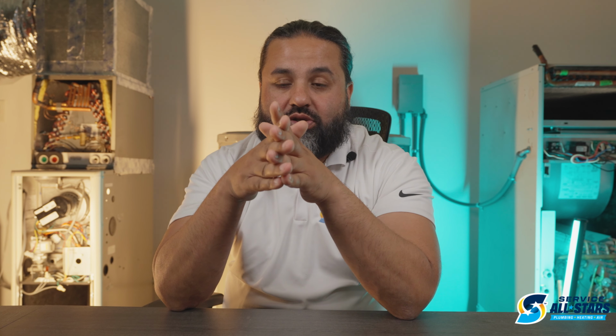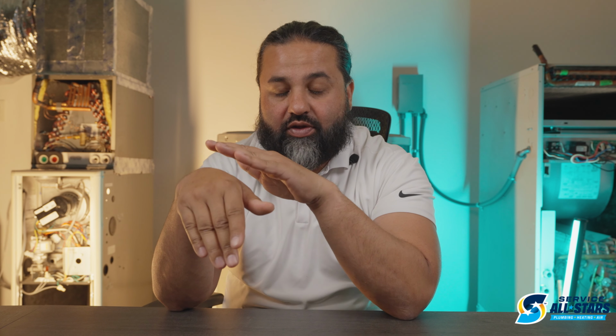The other thing about ductwork design is that it has to be installed properly. What I mean by that is that it definitely needs to be strapped up, because if it's just laying around there, what happens is in the attic, you have what's called your ceiling rafters. And if the ductwork is laying on the ceiling rafters, it's going to dip into the ceiling rafter. Well, every single dip, every single turn is impedance for the airflow. And what I mean by that is, think about driving a car, right?